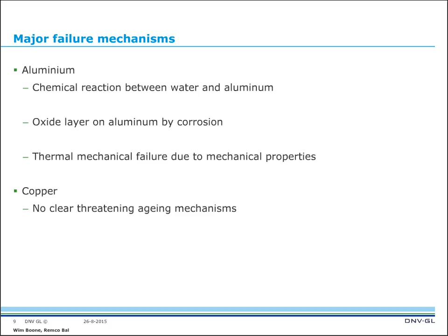Thirdly, thermomechanical failure due to mechanical properties. There is far more expansion with aluminum than copper, and that gives thermomechanical stresses with possible related failures. For copper, we could not find a clear threatening aging mechanism.